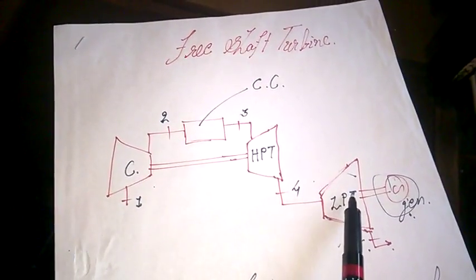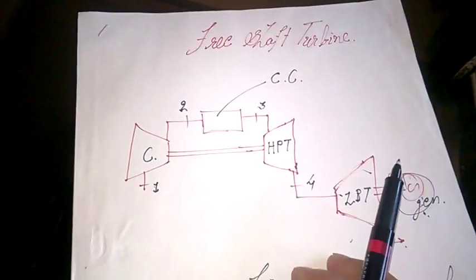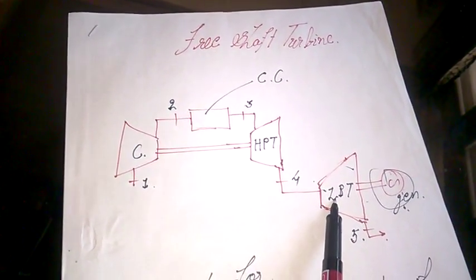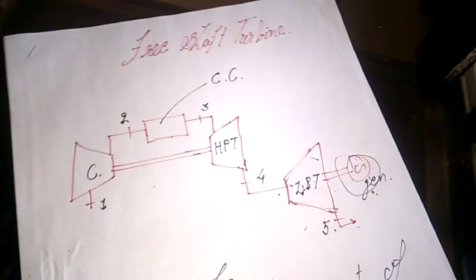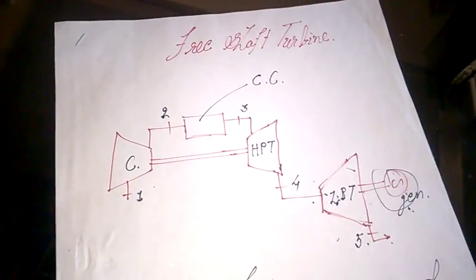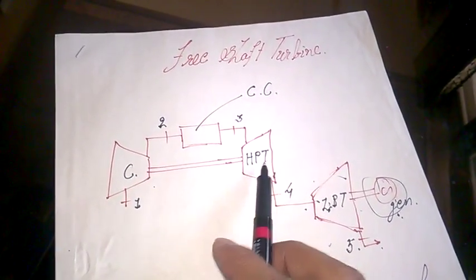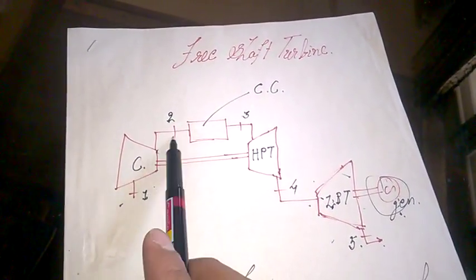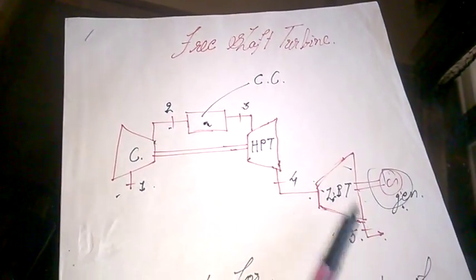As the name suggests — free shaft — there are basically two turbines: a high pressure turbine and a low pressure turbine. We take the power and generate the power from the low pressure turbine. The shaft of this turbine is not connected with the compressor, which is why it is called a free shaft turbine. In a gas turbine there is a compressor, then a combustion chamber, then the turbine. Air comes in, gets compressed, enters the combustion chamber where fuel is burned, and then goes straight to the turbine.